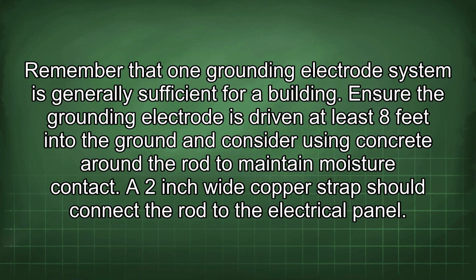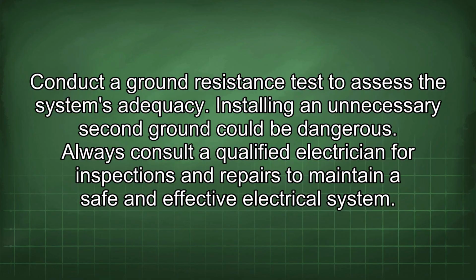Remember that one grounding electrode system is generally sufficient for a building. Ensure the grounding electrode is driven at least 8 feet into the ground and consider using concrete around the rod to maintain moisture contact. A 2-inch wide copper strap should connect the rod to the electrical panel. Conduct a ground resistance test to assess the system's adequacy. Installing an unnecessary second ground could be dangerous. Always consult a qualified electrician for inspections and repairs to maintain a safe and effective electrical system.